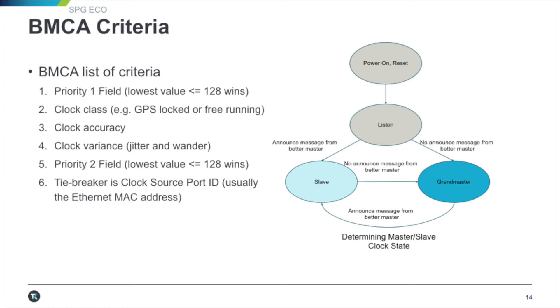The BMCA list of criteria for determining which clock is best master: Priority 1 field — the lowest number below 128 wins, so you can configure that within the device to force it to be grandmaster. Class of the clock: is it GPS or free-running? GPS always wins. Clock accuracy — how stable is the clock? Clock variance — jitter and wander. If all those are equal, it drops down to priority 2, where the lowest value below 128 wins. You can configure priority 1 and priority 2, and which would step in to take over. A tiebreaker, which you'd try to avoid, is determined by the Ethernet MAC address of the hardware.